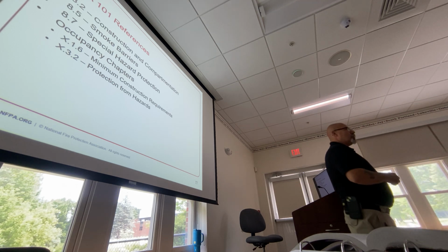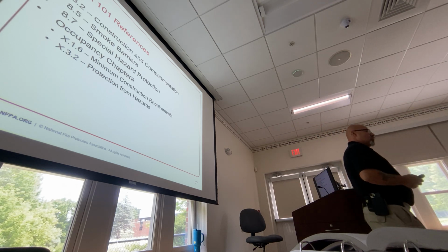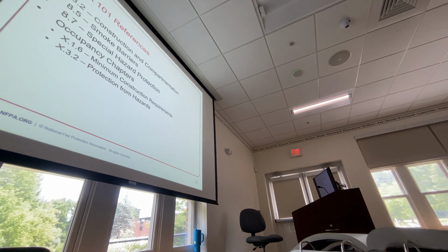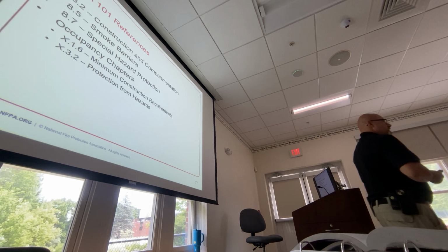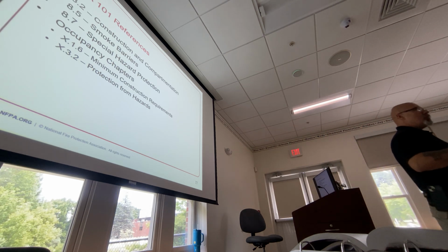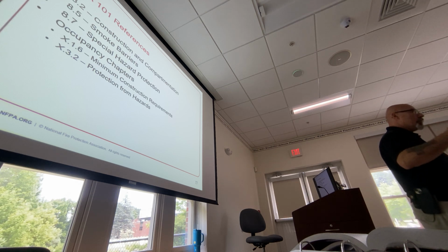So, in order to get that permitted, if I want to build a 3-story hospital, the best that I'm going to get is a type 2, right? But it all depends. Sprinkled or non-sprinkled. Okay, it has to be sprinkled. So that is how you find your construction type and whether you can do whatever you want to do with it.